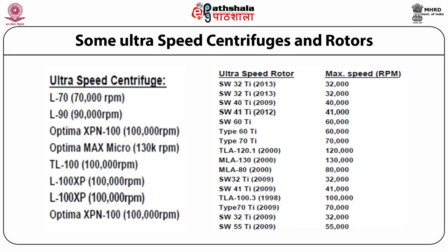Some ultracentrifuge models and their speed limits: the L70 model is capable of up to 70,000 rpm; L90 up to 90,000 rpm; Optima XPN 100 up to 100,000 rpm; Optima Max Micro up to 130,000 rpm; TL100 up to 100,000 rpm; L100 XP up to 100,000 rpm. Corresponding rotor models are listed with their year of market release and maximum speed — for example, SW32Ti was released in 2013 with a maximum speed of 32,000 rpm.